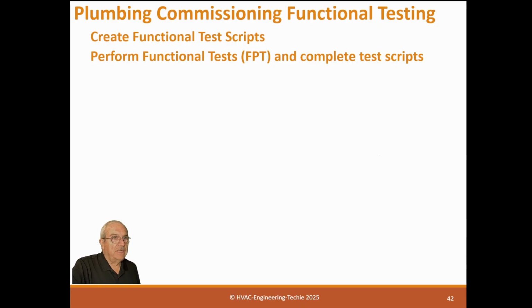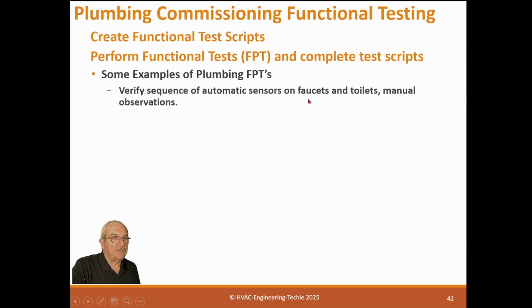So, functional test scripts and complete test scripts. Some examples of a plumbing functional performance: verify sequence of operation of sensors on faucets and toilets, by manual observation. When they install a touchless faucet, it needs to be adjusted for how many feet it detects before turning the water on. You know how irritating it is to go up to a laboratory sink, put your hands down, and nothing happens. You wonder why it doesn't come on, and finally it does. Well, that means it's not adjusted correctly. Or if you walk down the aisle and it comes on when you're not even near the fixture, that can be a problem. So during a test, you just list the fixtures, walk up to each fixture and put your hands down. If it doesn't come on, it's not adjusted correctly.